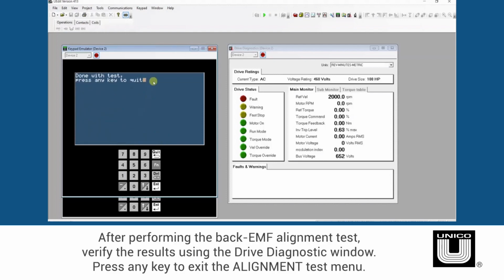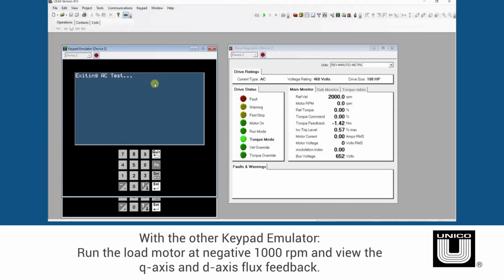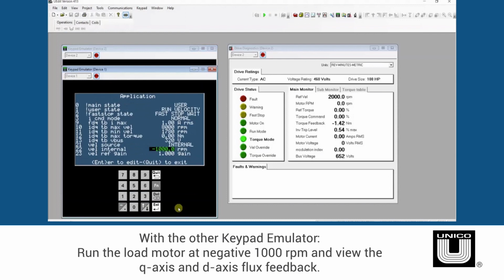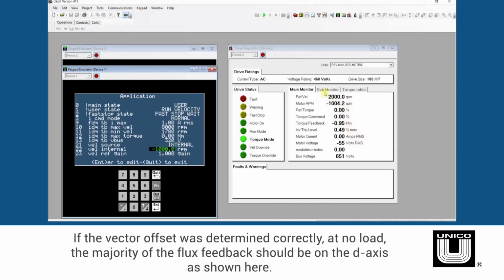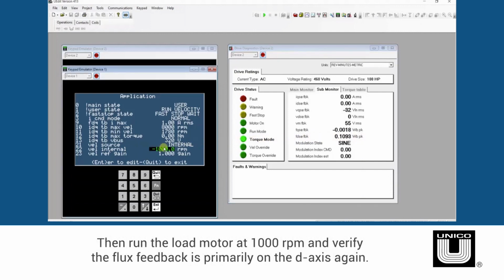After performing the back EMF alignment test, verify the results using the drive diagnostic window. To do this, run the load motor at negative 1000 RPM and view the Q-axis and D-axis flux feedback. If the vector offset was determined correctly at no load, the majority of the flux feedback should be on the D-axis as shown here. Then run the load motor at 1000 RPM and verify the flux feedback is primarily on the D-axis again.